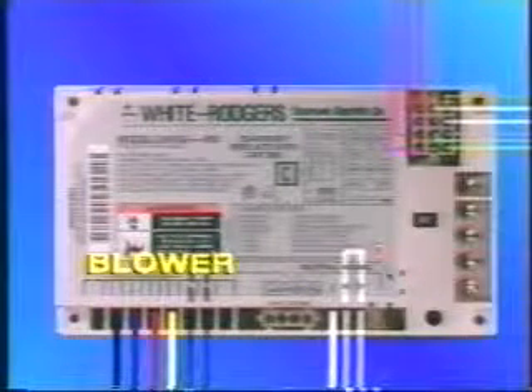All timing of blower fan operations are controlled by the integrated module. In some versions, the blower delay times can be set by the technician using dip switches on the front of the module. On some models, heat on delay and heat off delay can be set. Optional versions also include timing delays in cooling for both blower on and blower off.